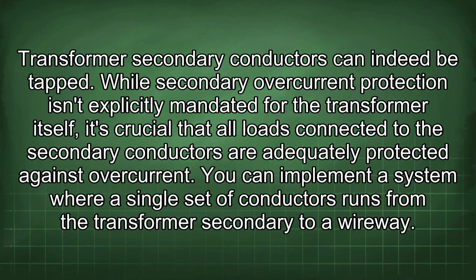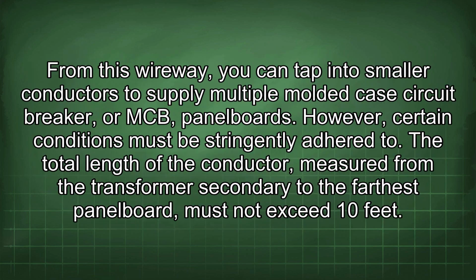Transformer secondary conductors can indeed be tapped. While secondary overcurrent protection isn't explicitly mandated for the transformer itself, it's crucial that all loads connected to the secondary conductors are adequately protected against overcurrent. You can implement a system where a single set of conductors runs from the transformer secondary to a wireway. From this wireway, you can tap into smaller conductors to supply multiple molded case circuit breaker, or MCB, panel boards. However, certain conditions must be stringently adhered to.